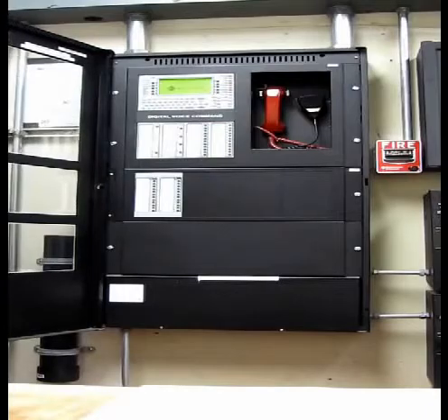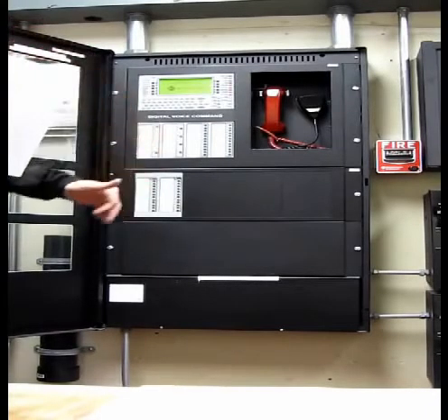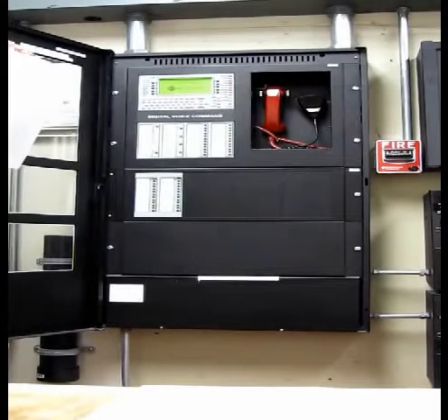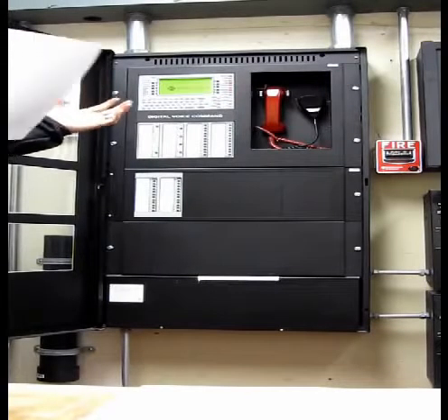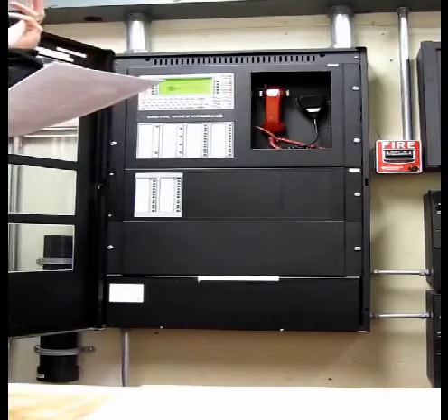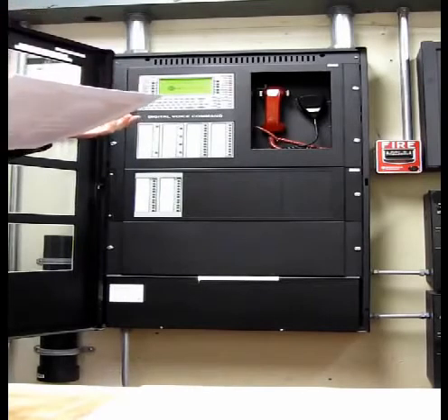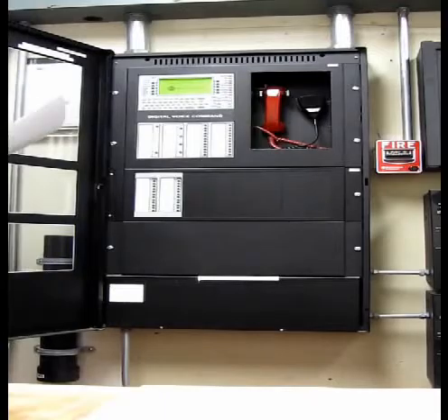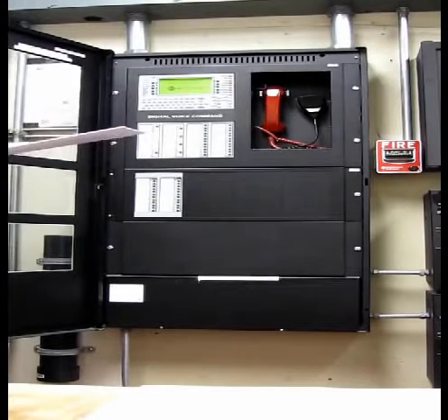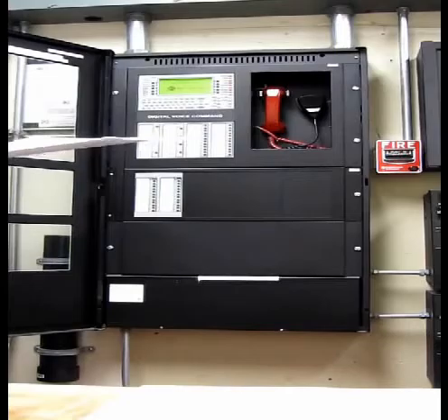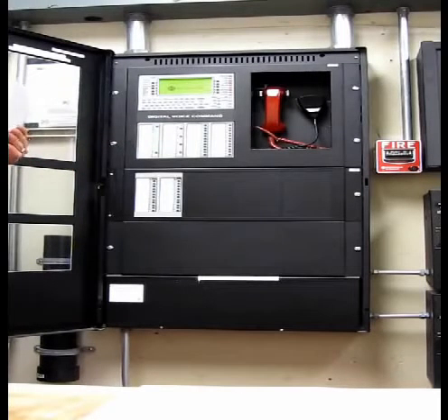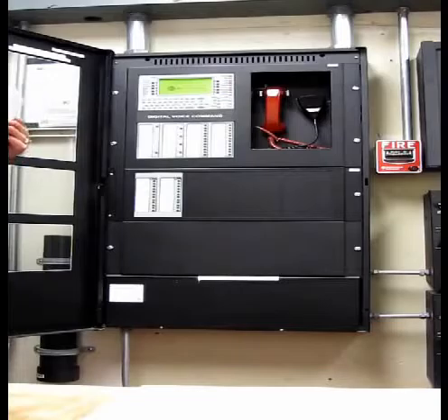If there's an alarm, it's an immediate thing. The panel's already sending a signal to our central station, and our central station's on the phone with the fire department. So if you find, let's say for example, you're doing some solder work and you forgot to cover a smoke, and you know it's a false alarm for sure, you can call this number and try to call the fire department off. Give the account number, say, hey, we have a false alarm, can you call off the fire engines. Most of the time it's not possible because they're already on their way, rolling, but it's worth a shot if you know it's a false alarm.